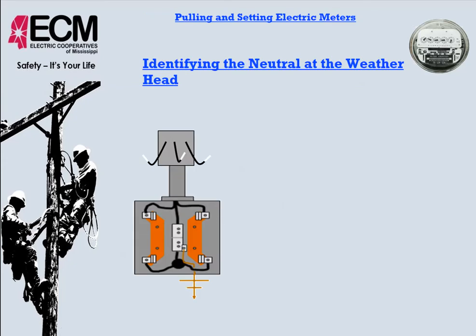Okay. All right. So here's another thing. So we've inspected our meter base. Everything's good with it, and we need to think about hooking it up and setting our meter. Okay. So when our load side here is hooked up and the wires come out the top of our weatherhead, a lot of times they'll put some white tape on one and white tape down here, but we really don't need to trust that. We need to be able to identify our neutral so that we can be sure that we're hooking up the right voltages in the right places.